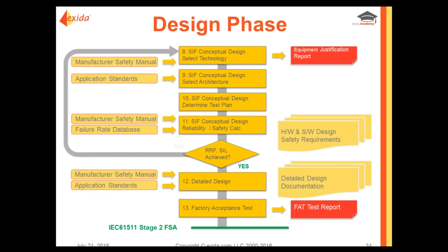Once you know if you need a SIF or a SIL analysis done, you are then moved to the design phase of the safety life cycle. And this is also called the realization phase. It begins with the conceptual design of the safety instrumented system based on the safety requirement specification that we just created out of documentation. You look at the desired technology and you choose what sensor, what logic solver, or final element, or combination of all of them to be in your SIF.